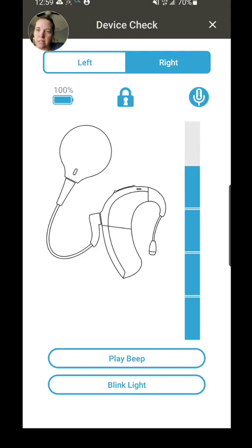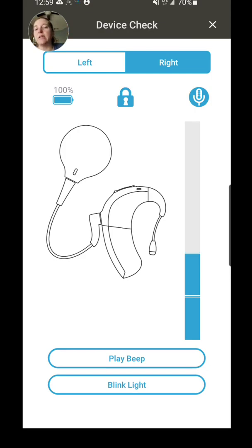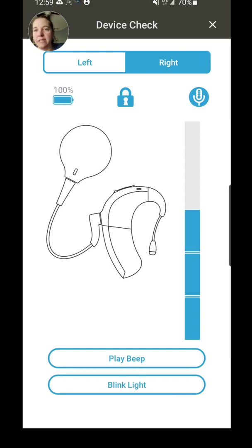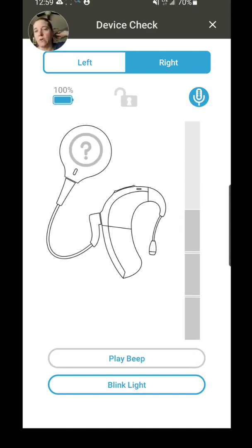So this is going to be related to how much environmental sound is coming in. So if you see, as you increase noise, the microphone indicator pops up. So you're seeing how much environmental sound is being picked up by the microphone. If for some reason that T-mic is broken, you will see that the T-mic will be grayed out and that will indicate that the T-mic is not functional.